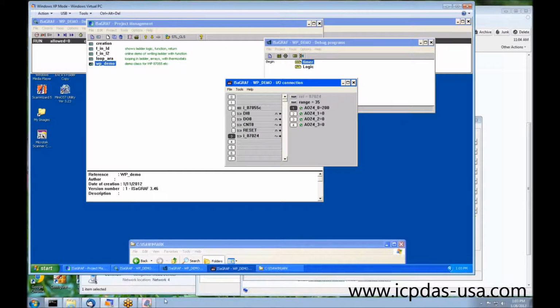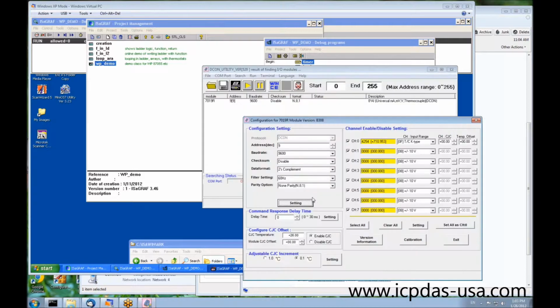It's showing 29C. Let's go and force a little bit of value back here. There. 0. Let's make it 200 counts. Right. And let's look at DCON Utility. And now it's showing 711 degrees C. The room is on fire. We don't like that so much.